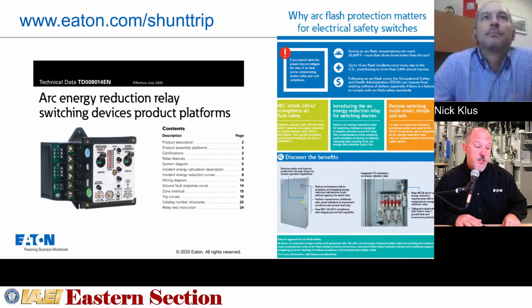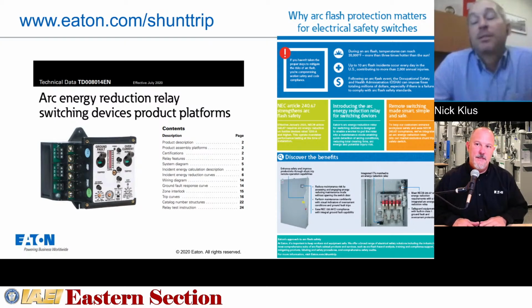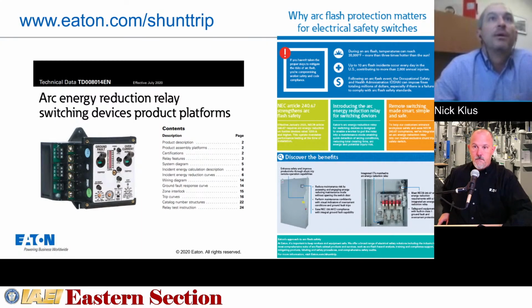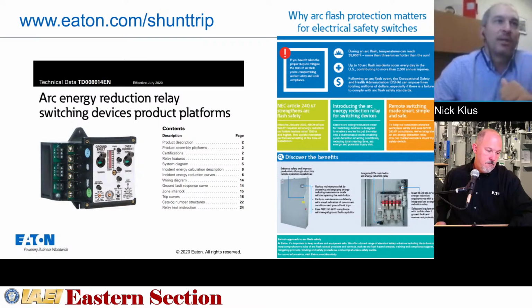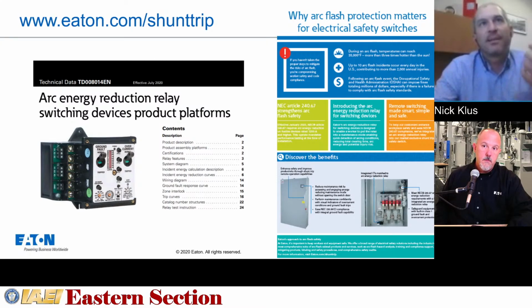Another question for you from a switch perspective. Can you open the switch without turning it off and service it energized? Can you open the switch without turning it off? Yes, part of UL 98 does require that, as safety switch manufacturers, we have a defeat mechanism that would allow you to do that. Our heavy duty switches as standard, when you turn a switch on and the handle goes to the up position, have an interlock that latches your door shut, because obviously 99% of the time that you're around that switch with it on, you want that door to be closed and nobody to be able to gain access to it.